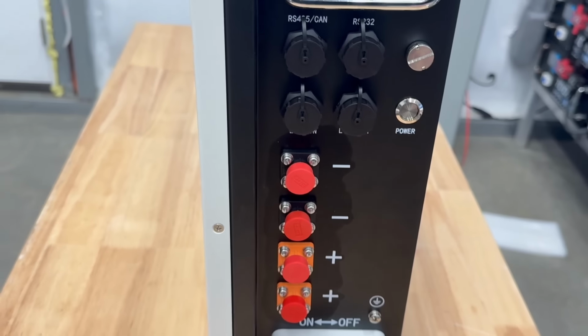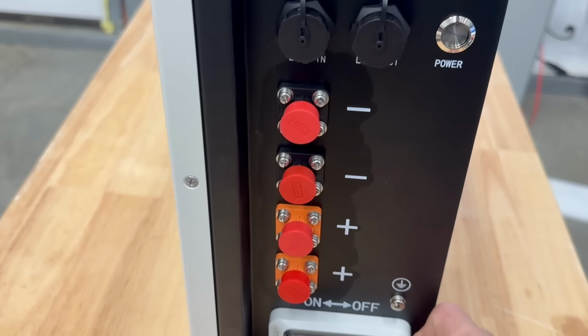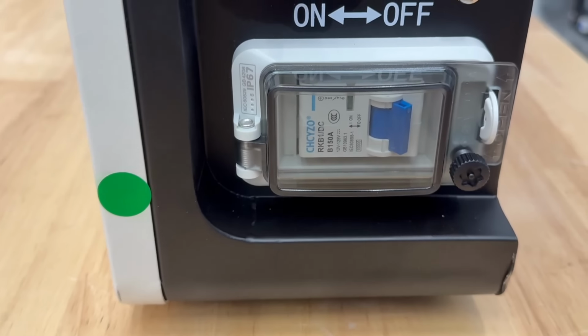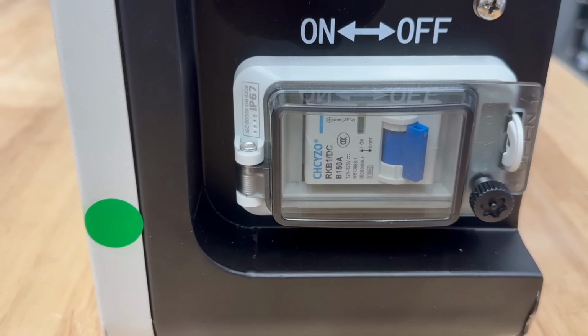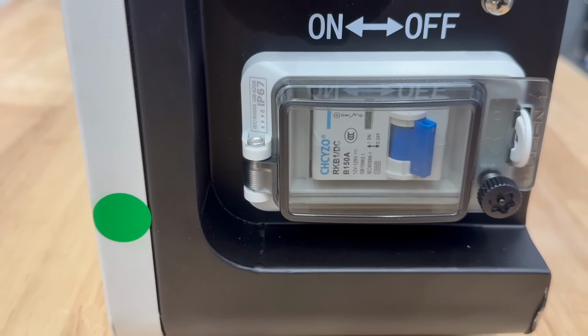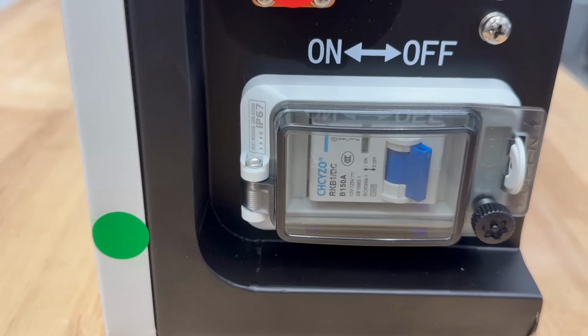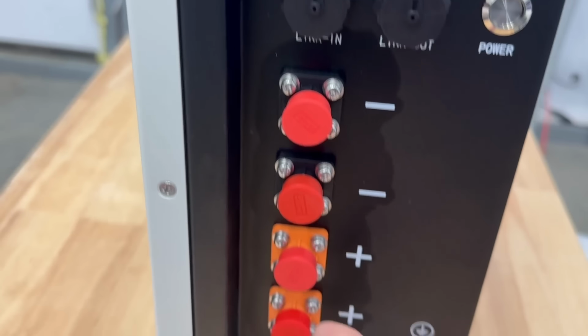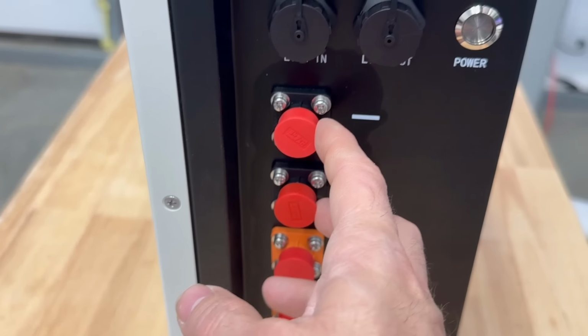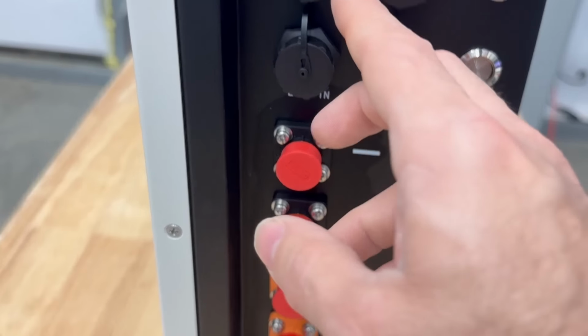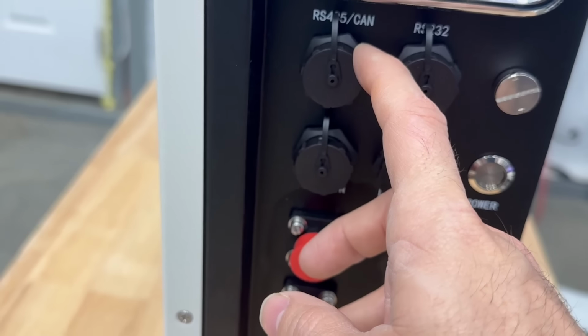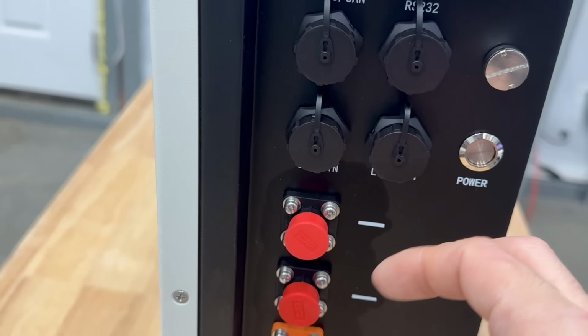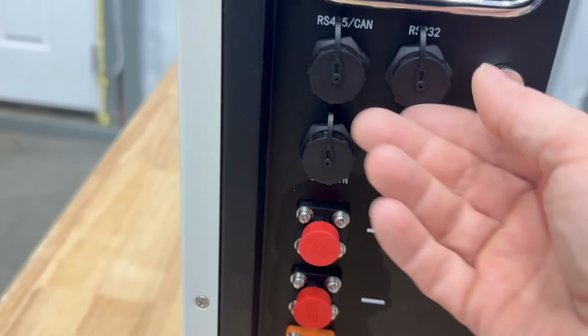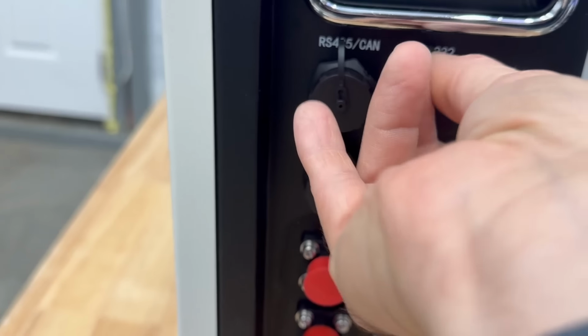On the side, you've got your power button and your circuit breaker. The circuit breaker is made by CHC-YZO, and it is a 150 amp breaker. You have two positive connections, two negative, once again those Amphenol, and you have RS485 and RS232 connections on this.